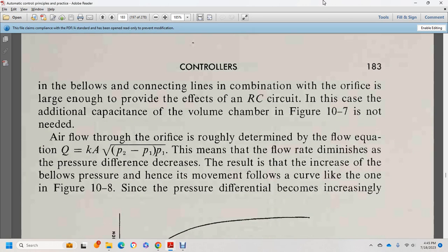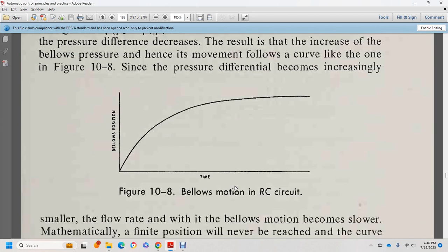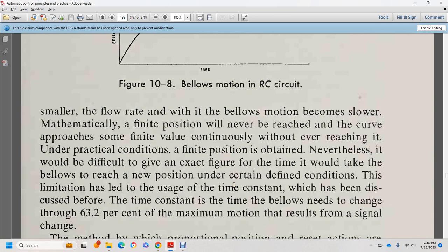The airflow through the orifice is roughly determined by the equation Q = K × A × √(P1(P2 − P1)). This means the flow rate diminishes as the pressure difference decreases, resulting in increasing bellows pressure. As shown in figure 10-8, as the pressure differential decreases and the bellows approaches its final position, the RC circuit makes the flow rate smaller and the bellows motion slower. Mathematically, the final position is never actually reached — the curve approaches it asymptotically.